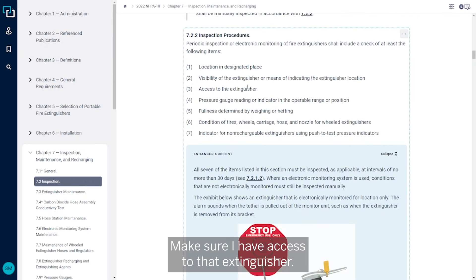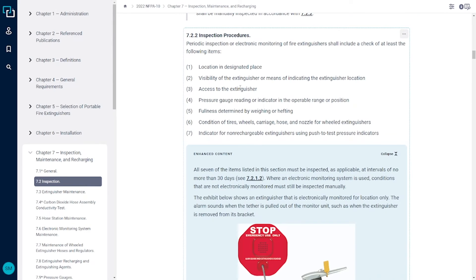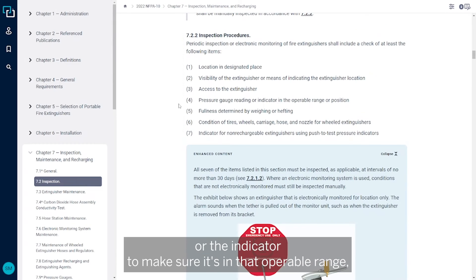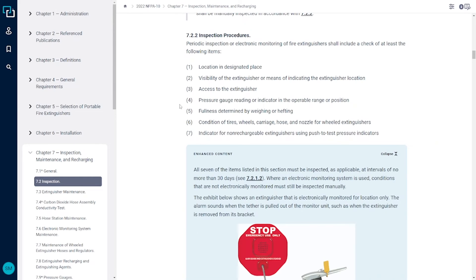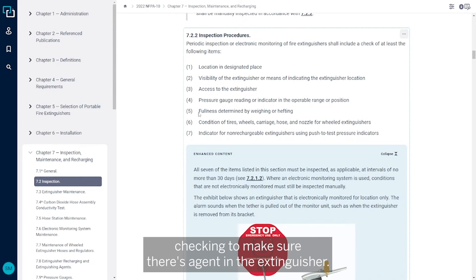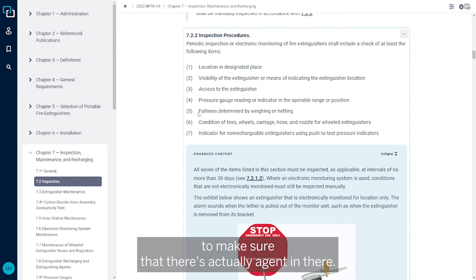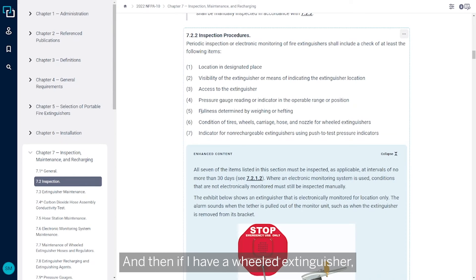Then checking the pressure gauge reading or the indicator to make sure it's in that operable range. Checking to make sure there's agent in the extinguisher, so that's by either lifting it or weighing it or some means to make sure that there's actually agent in there.